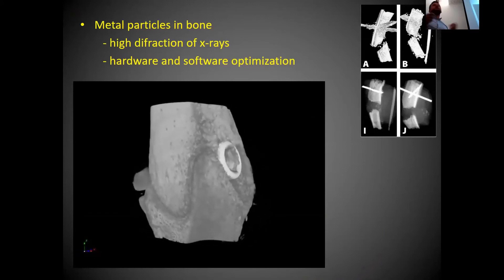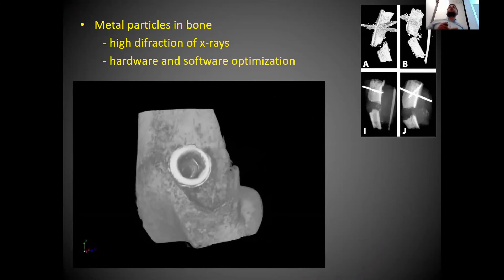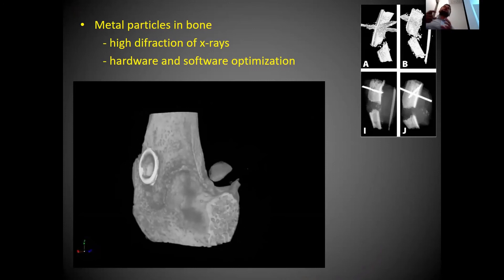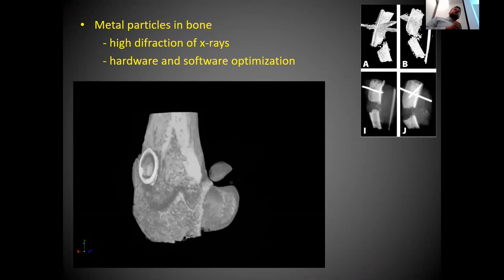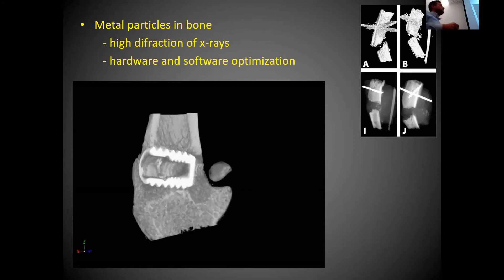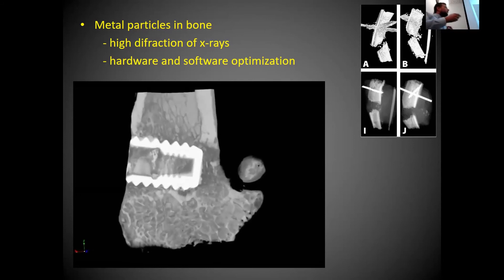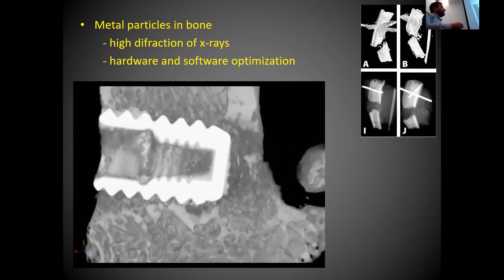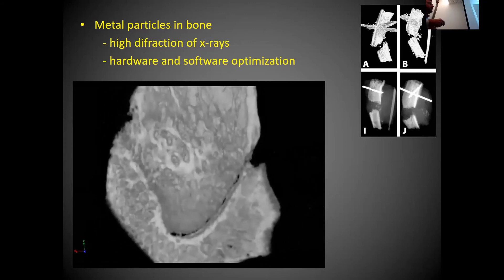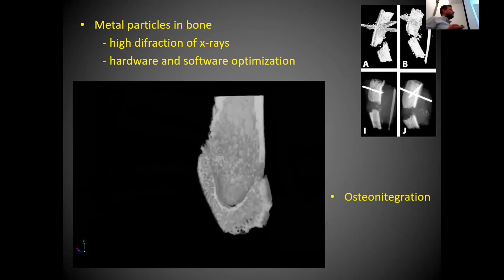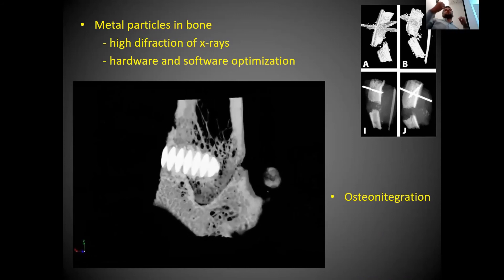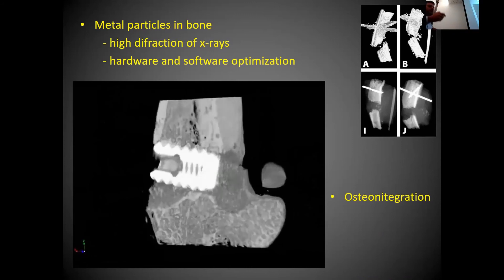Metal particles within bone can also be visualized. Metal diffracts X-rays to a much greater extent than bone, so you need to apply some optimizations during scanning and reconstruction to avoid artifacts. If the scan is good, you can clearly see whether a metal object has integrated into bone — osteointegration — and you can quantify this.